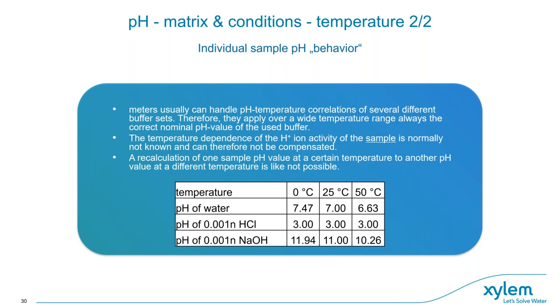A practical industrial example: an online product sample is measured directly at the process at 70°C, and later a person takes the sample to the lab where it cools down. The values are different, and there is no right or wrong — it is simply the individual temperature behavior of that sample. To make values at different temperatures comparable, you could measure the product at various temperatures and create a correction diagram. In such industrial applications, reproducibility is often more important than absolute accuracy.